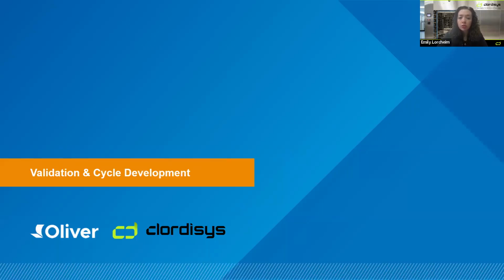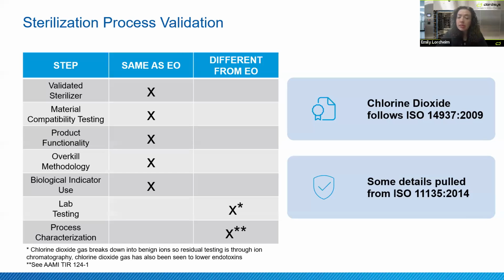Now we're going to briefly talk about validation and cycle development. Again, this is very product specific, but we'll give a brief overview. So it's basically the same process as you would follow with ethylene oxide. We're going to follow ISO 14937 instead of ISO 11135. However, it's almost identical with only a few key differences, being the lab testing, mainly in terms of residuals, where our residual test method follows ion chromatography testing, looking for the potential byproducts of chlorite, chlorate, and chloride. And also, process characterization is different because it's a different sterilant. However, there is a new AAMI TIR, which is TIR 124-1, and this is how chlorine dioxide relates and is applied to ISO 14937. So it makes it a very simple process, especially when you're familiar with ISO 11135.